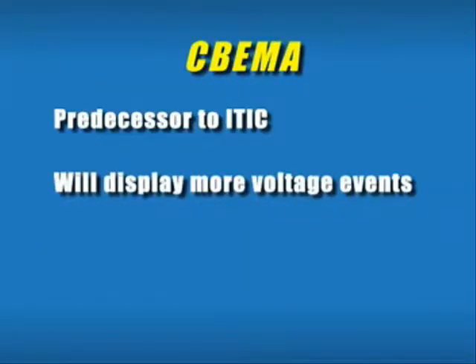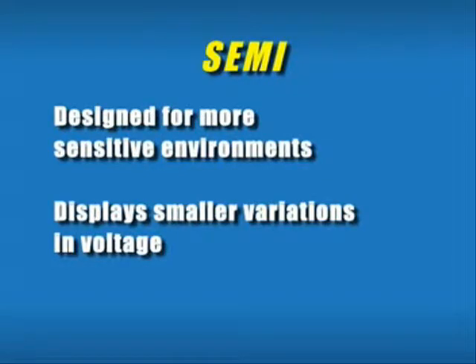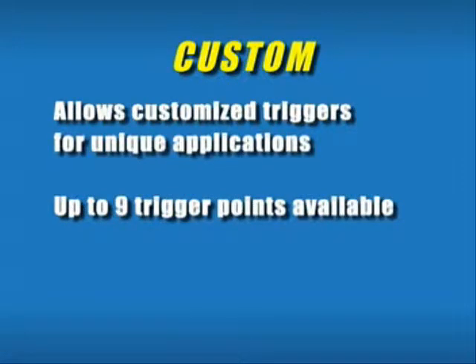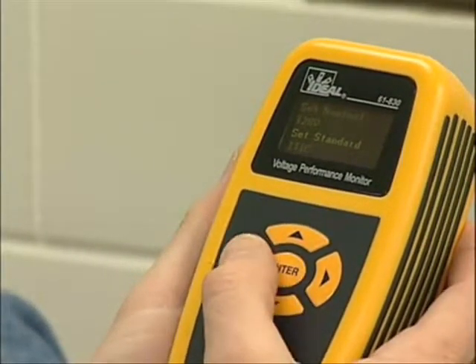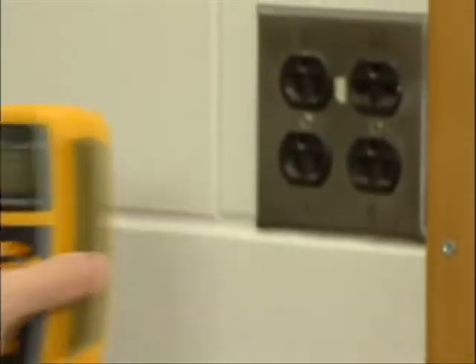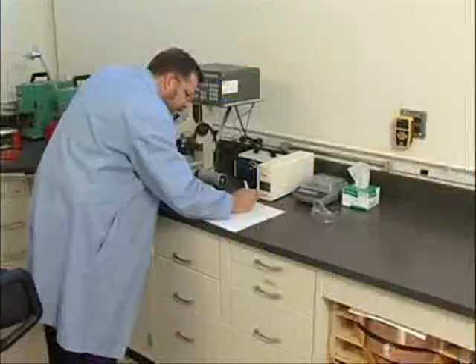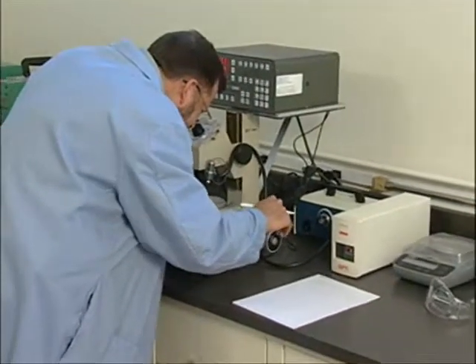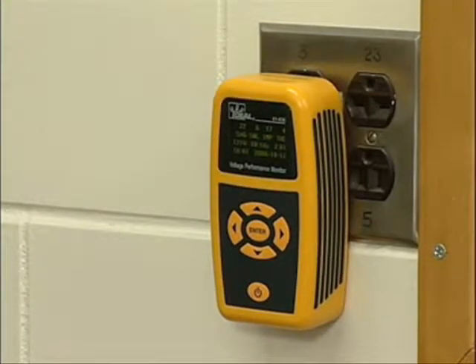The CBEMA standard allows for more events to be seen. To see everything on the line, choose the SEMI standard. And for power utility circuits up to 240 volts AC, you can choose the ANSI standard. Based on experience and personal preferences, you can also create and maintain a library of custom standards and results. Once the standard is selected, plug the voltage performance monitor into the same receptacle as the failing equipment or survey site. By connecting close to the input, you'll be measuring exactly the same voltage events affecting the specific piece of equipment on its actual branch circuit. Then the unit will automatically begin monitoring for events.